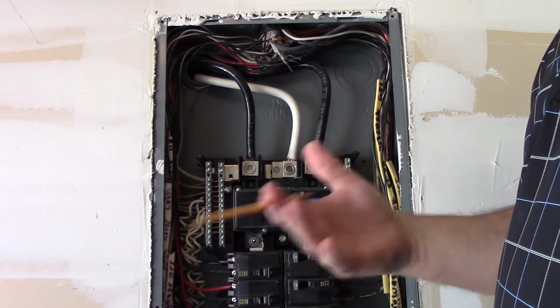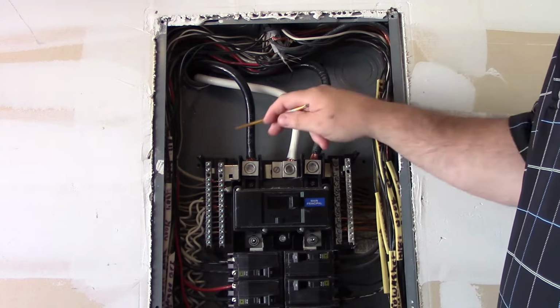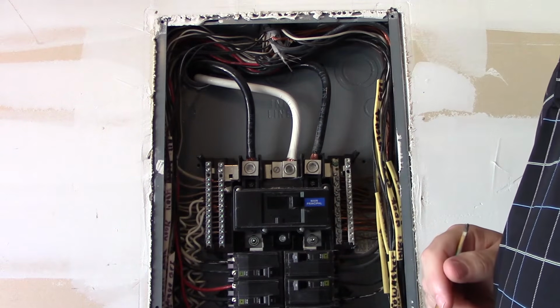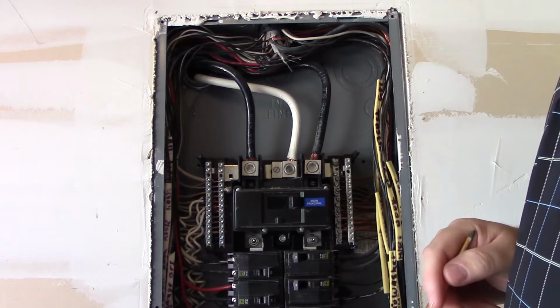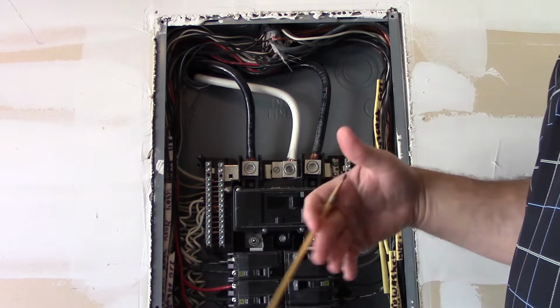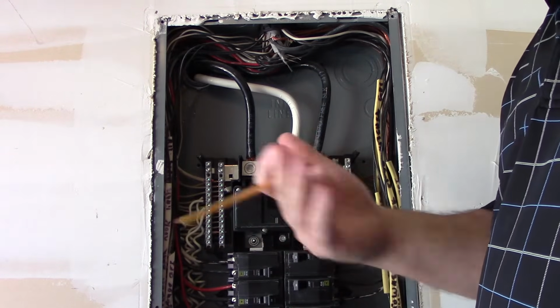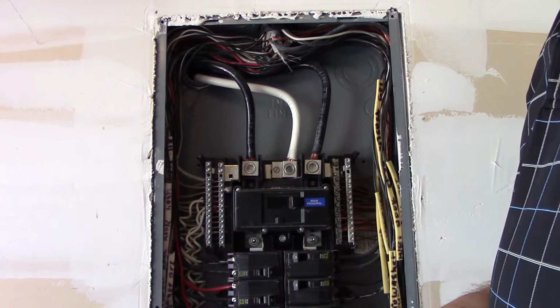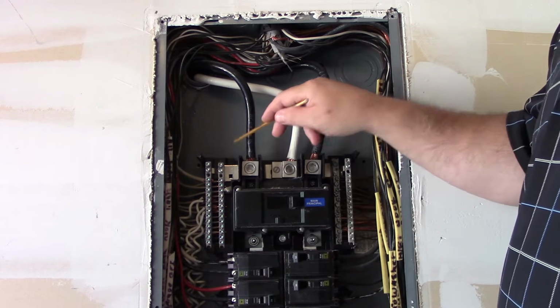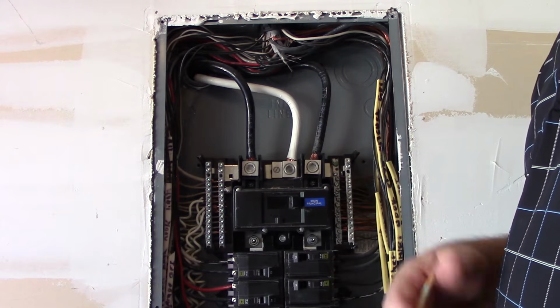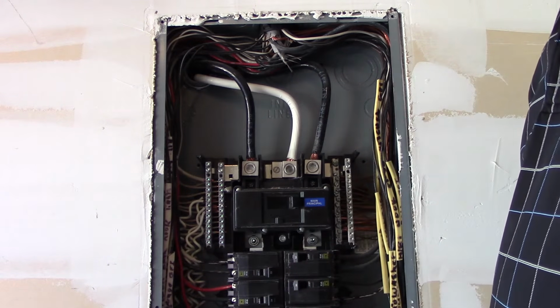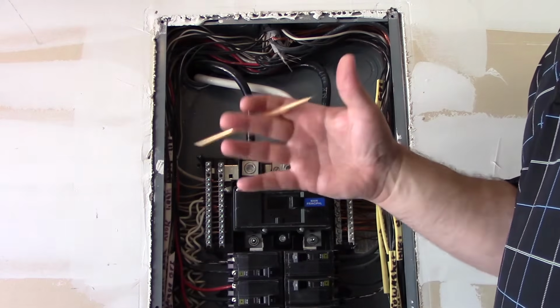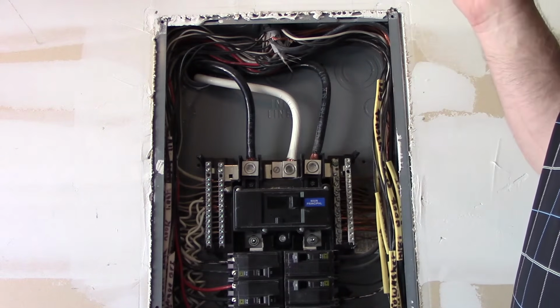So that's how you're able to use that smaller table or that calculation now to determine the minimum size that you need for a 200 amp service. So that's how you would do it in this case right here. There's enough diversity inside of a residence. Not all things are on at the same time. The loads are always a little different. So that diversity allows you to use that table that allows a 2/0, which is really only good for 175 amps, to be used on a 200 amp rated service because of that diversity. It's still okay. All right, not a problem.